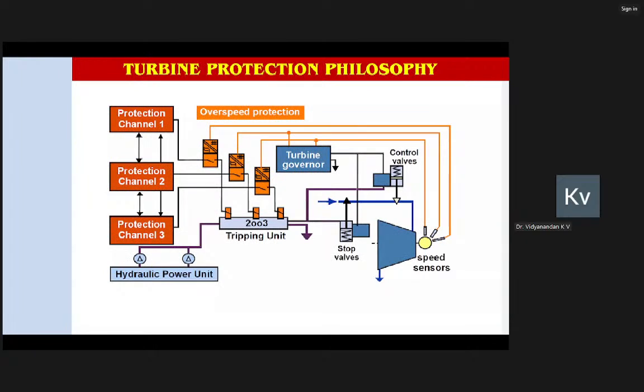Now coming to the protection, because turbine and generator are the most critical components of the power system. Even though behind the turbine there is a boiler, as far as the power grid is concerned, the grid is not directly seeing the boiler. The power grid is directly seeing the generator, and the generator is driven by the turbine. So these two components are the most important from the power system point of view. And for protection purposes, these systems have multiple levels of protection schemes.